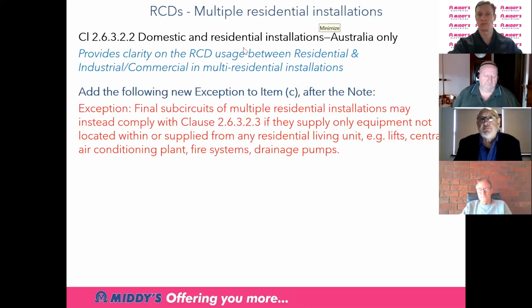So what we've had to do is we provided some sort of demarcation. So we put in that exception in red to say that if you have equipment that is not located or supplied from any residential living unit, so that's a lift, central air conditioning plants, fire system, drainage pumps, that sort of thing, if it's not supplying any socket outlets, then what you do is you apply the industrial or non-residential rule. If it supplies a residential installation within that complex, it may be the swimming pool area or a common sports area or a barbecue area, well then that comes under the residential. So we tried now to give a decent demarcation between residential and non-residential in those apartment type complexes. Next one.